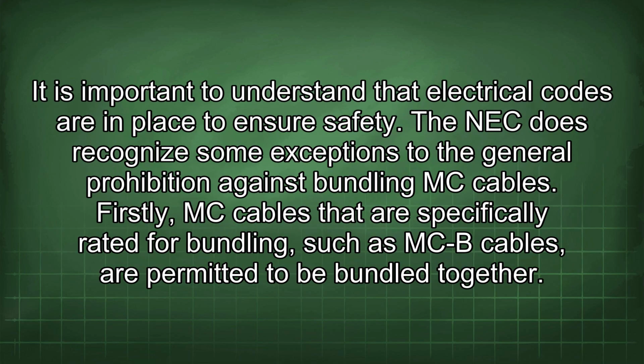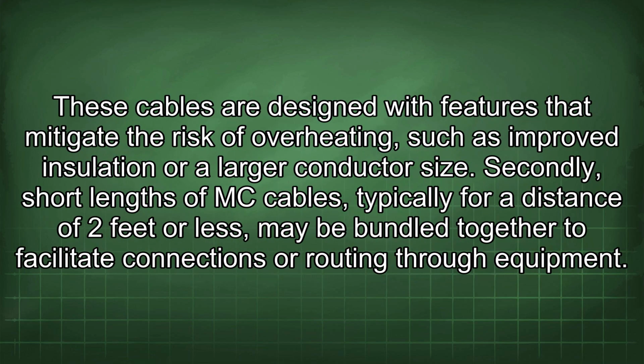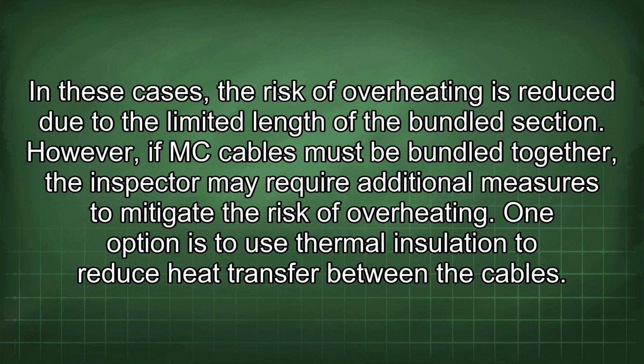It is important to understand that electrical codes are in place to ensure safety. The NEC does recognize some exceptions to the general prohibition against bundling MC cables. Firstly, MC cables that are specifically rated for bundling, such as MCB cables, are permitted to be bundled together. These cables are designed with features that mitigate the risk of overheating, such as improved insulation or a larger conductor size. Secondly, short lengths of MC cables, typically for a distance of 2 feet or less, may be bundled together to facilitate connections or routing through equipment. In these cases, the risk of overheating is reduced due to the limited length of the bundled section.